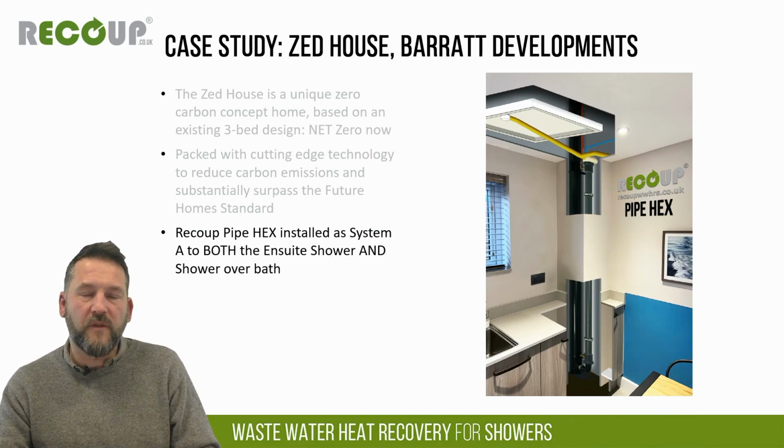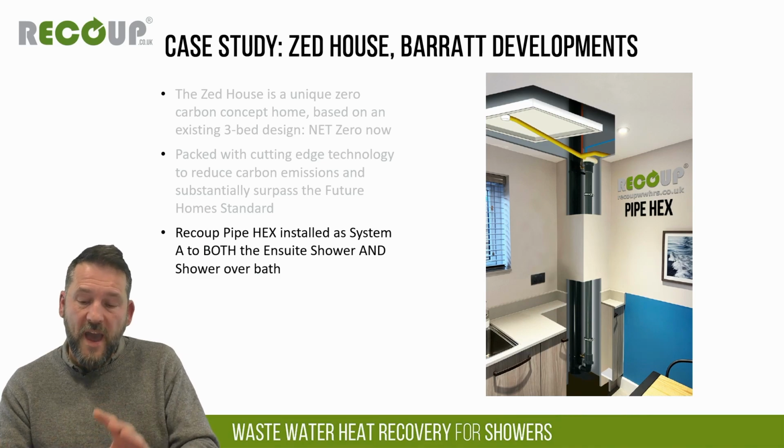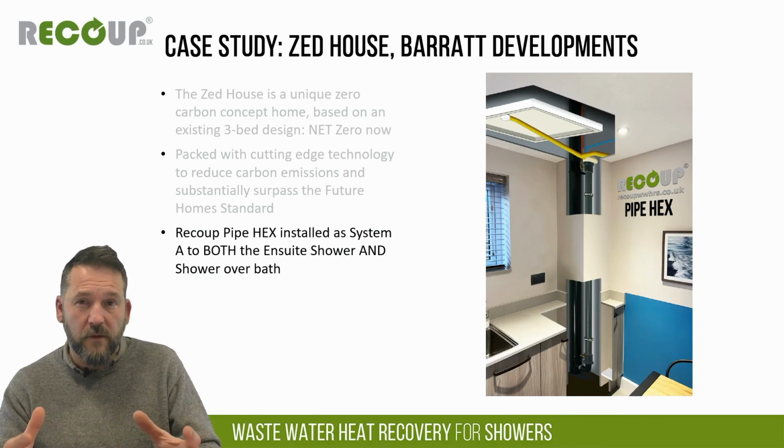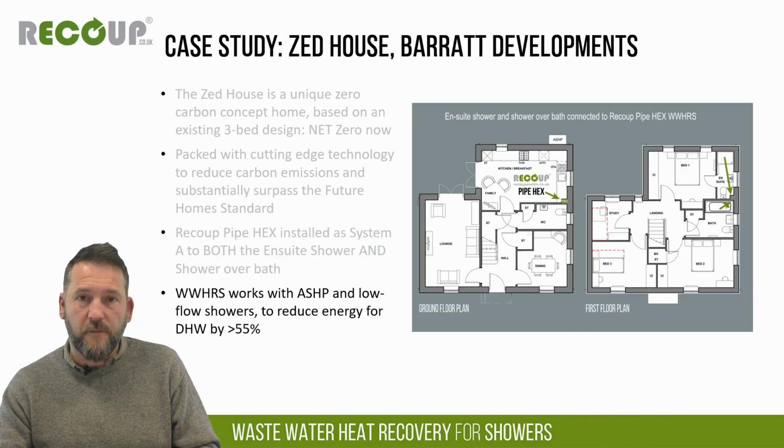What's again notable of this, it's a highly efficient fabric, but the hot water use is still being monitored here. Air source heat pump generated hot water with a Kelder low flow shower on the ensuite, down to I think about 5.5 litres per minute shower flow rate, and then a standard flow restrictor on the thermostatic mixer shower over bath on this one, and the wastewater heat recovery is working perfectly well. So we really are showing here that wastewater heat recovery is a future-proof technology for homes going forwards. Again, just very simple to design in.